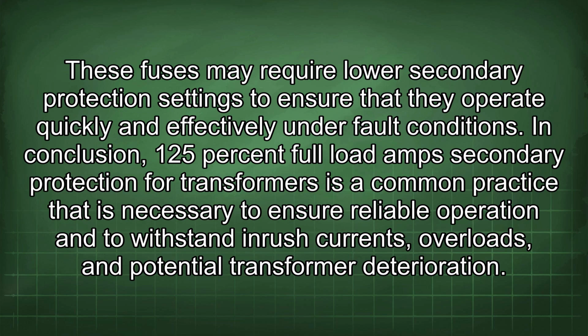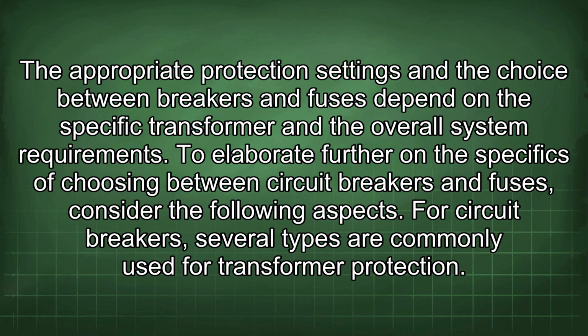In conclusion, 125% full load amp secondary protection for transformers is a common practice that is necessary to ensure reliable operation and to withstand inrush currents, overloads, and potential transformer deterioration. The appropriate protection settings and the choice between breakers and fuses depend on the specific transformer and the overall system requirements. To elaborate further on the specifics of choosing between circuit breakers and fuses, consider the following aspect.